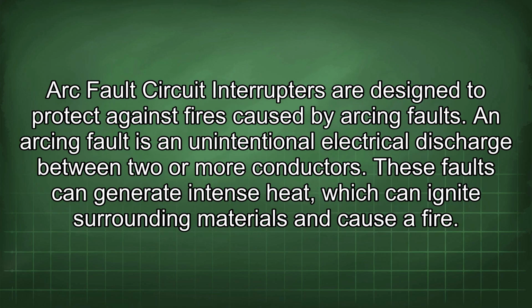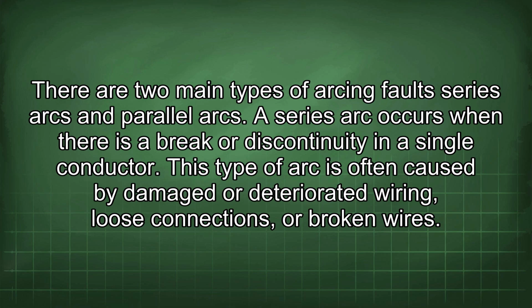Arc fault circuit interrupters are designed to protect against fires caused by arcing faults. An arcing fault is an unintentional electrical discharge between two or more conductors. These faults can generate intense heat, which can ignite surrounding materials and cause a fire. There are two main types of arcing faults: series arcs and parallel arcs. A series arc occurs when there is a break or discontinuity in a single conductor. This type of arc is often caused by damaged or deteriorated wiring, loose connections, or broken wires.